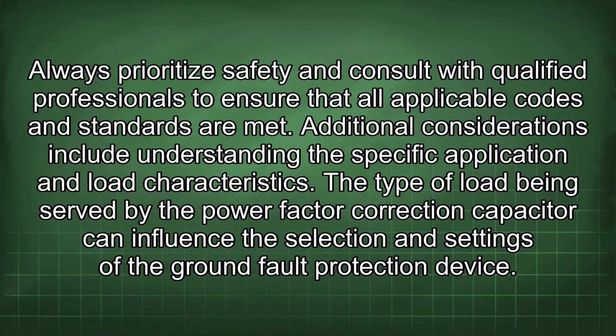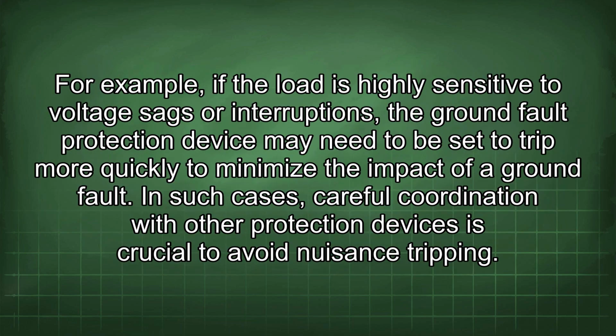Additional considerations include understanding the specific application and load characteristics. The type of load being served by the power factor correction capacitor can influence the selection and settings of the ground fault protection device. For example, if the load is highly sensitive to voltage sags or interruptions, the ground fault protection device may need to be set to trip more quickly to minimize the impact of a ground fault. In such cases, careful coordination with other protection devices is crucial to avoid nuisance tripping.